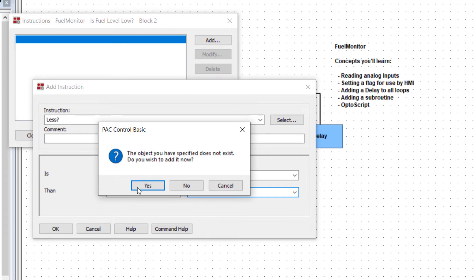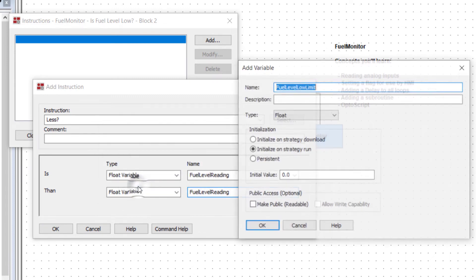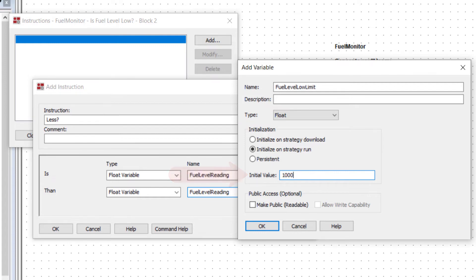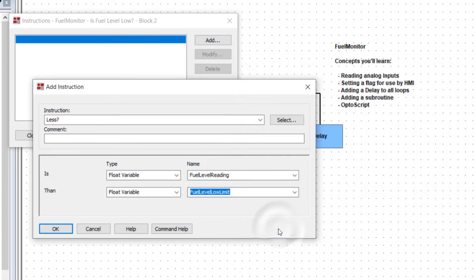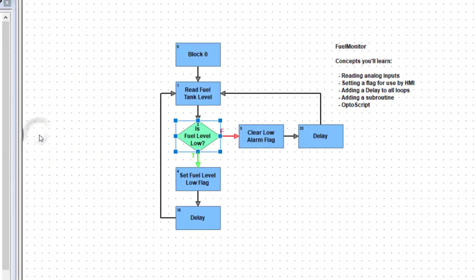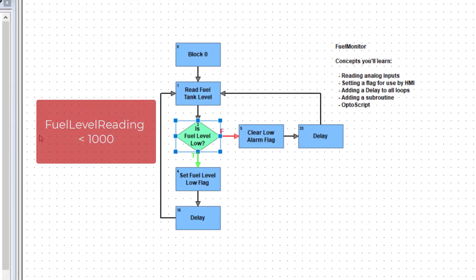Create the new variable and this time initialize it to 1000 to represent 1000 gallons as a low limit for our fuel tank. Click OK to create the variable. Click OK and then close. If the fuel level read is less than 1000, we'll exit true from the condition block and set a flag variable to true.